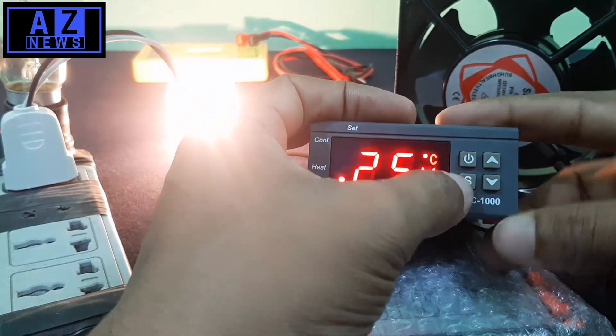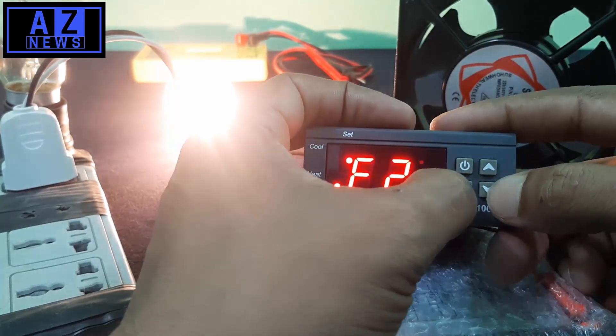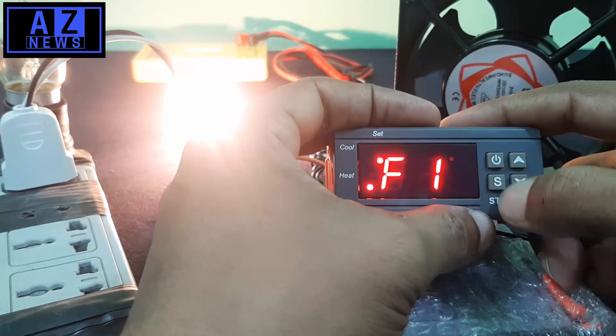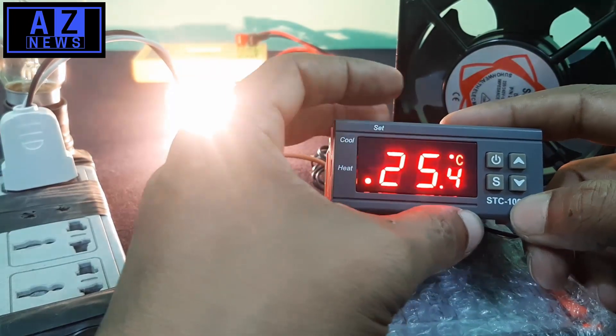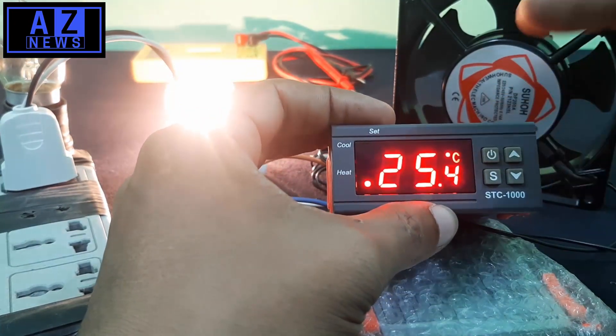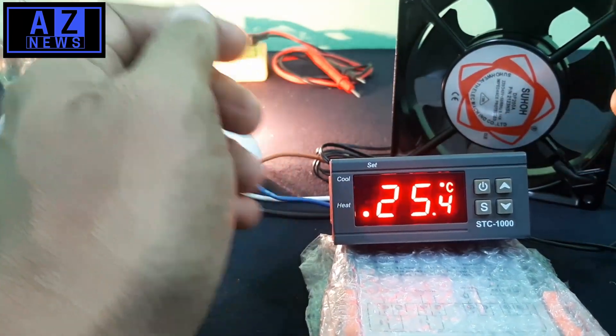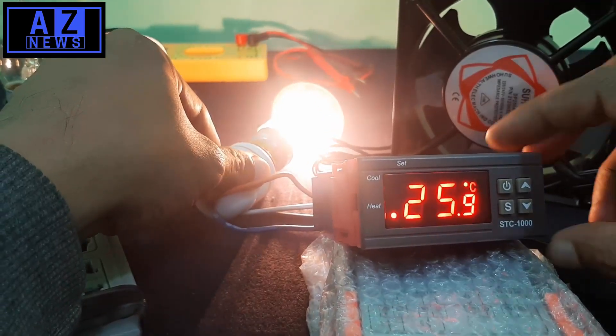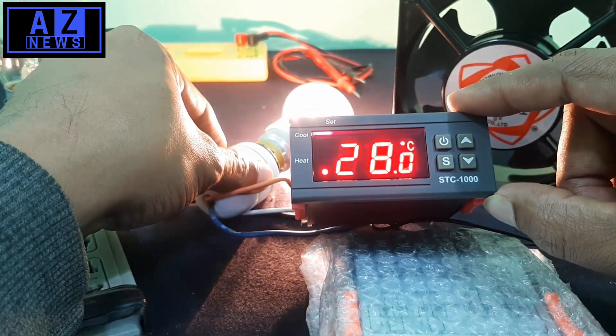To change the fraction value, I should navigate the menu and change it. You can see that my fraction value is now minus 1. I have set the maximum temperature to 37.7 degrees. The fraction value means the range is from 37.7 to 36.7 degrees. Now I can test this with my temperature conditions by inserting the bulb with the sensor attached.